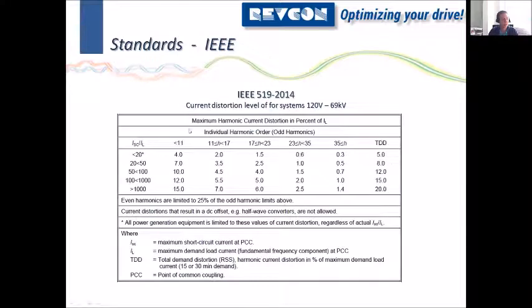to this one, on the left side, we will see the short circuit current divided by the load current. And this will give you information about the strength of your network. So IL, we already defined that's the load current, the fundamental part of the load current. But this part, the short circuit current, that can be the tricky one to find. So in order to define if I need harmonic mitigation, if I need 20%, 5, 8, 12, 15, and so on, first of all, I need to define what kind of relationship I have between short circuit current and load current. And that can be a very tricky point.